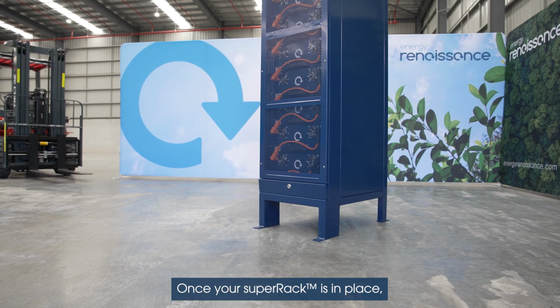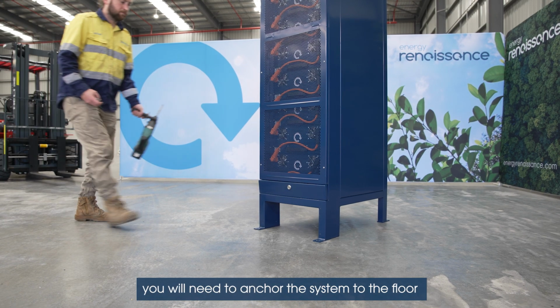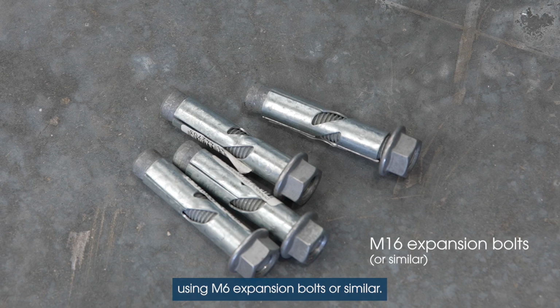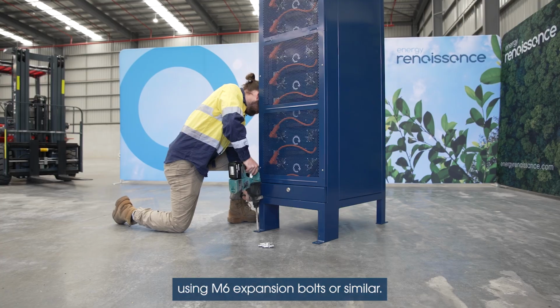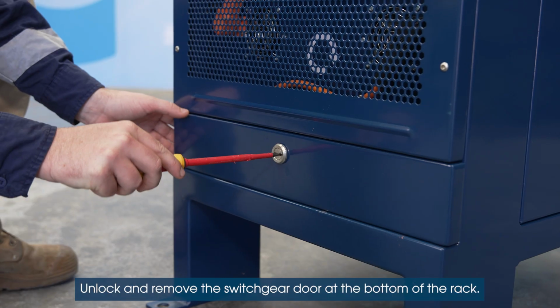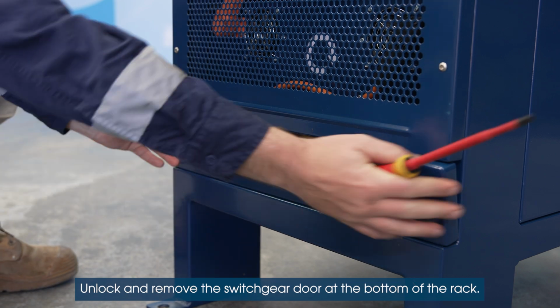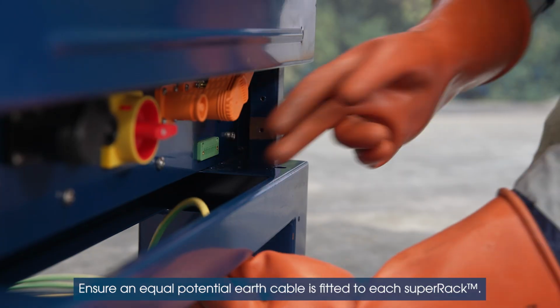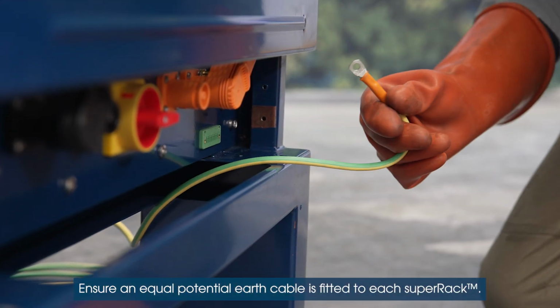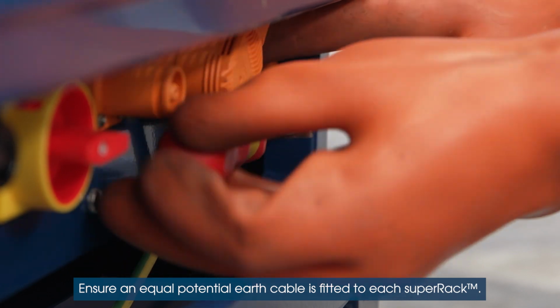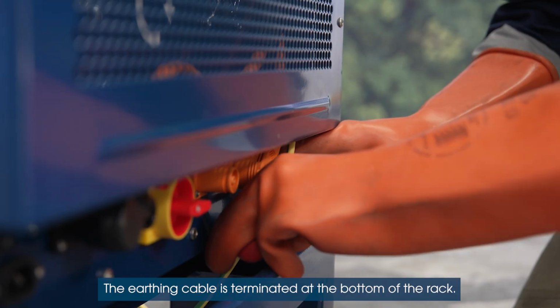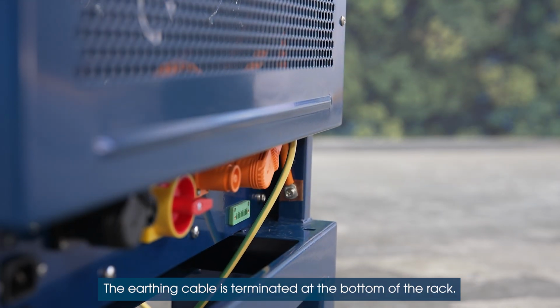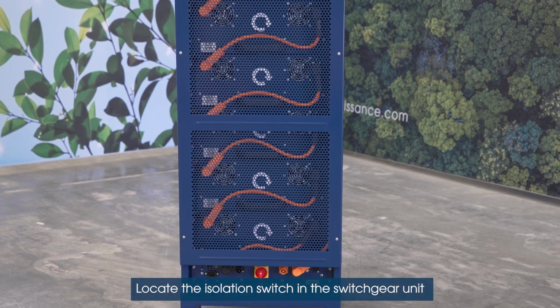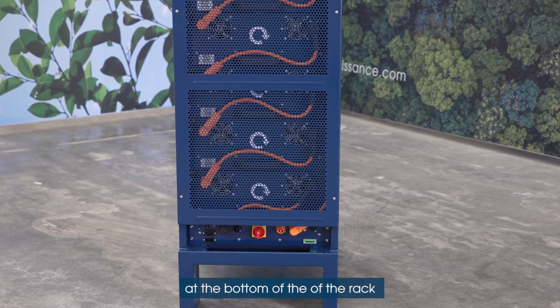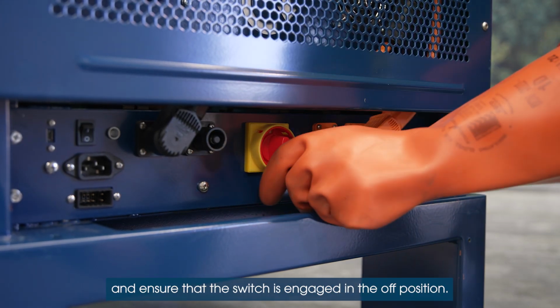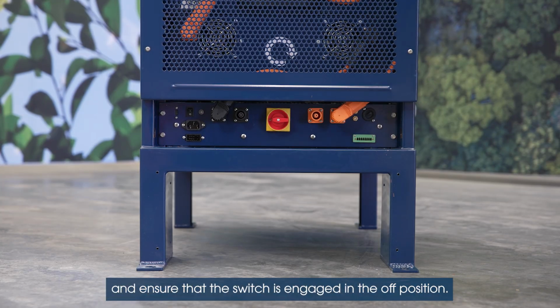Once your superRack is in place, you will need to anchor the system to the floor using M6 expansion bolts or similar. Unlock and remove the switchgear door at the bottom of the rack. Ensure an equal potential earth cable is fitted to each superRack. The earthing cable is terminated at the bottom of the rack. Locate the isolation switch in the switchgear unit at the bottom of the rack and ensure that the switch is engaged in the off position.